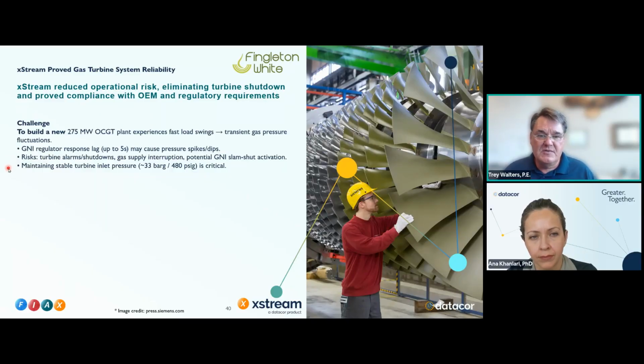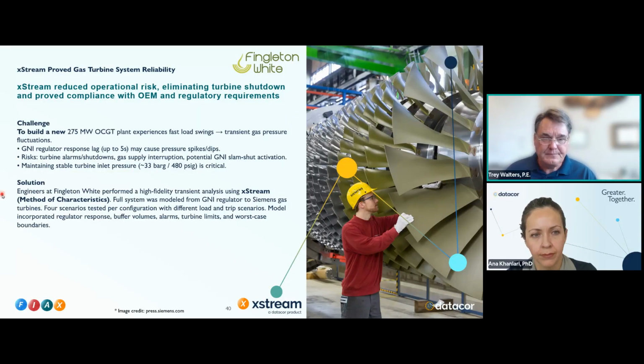And just what they want to do is maintain stable turbine inlet pressure. It's critical. And so if you have upsets to your system, especially if one of the turbines is going down or starting up, are they impacting the other 4 turbines that are in operation? And they're trying to keep things within an operational limit here so they can maintain operation. And so they used xStream to evaluate those different cases. And so I'll tell you how that worked out for them.